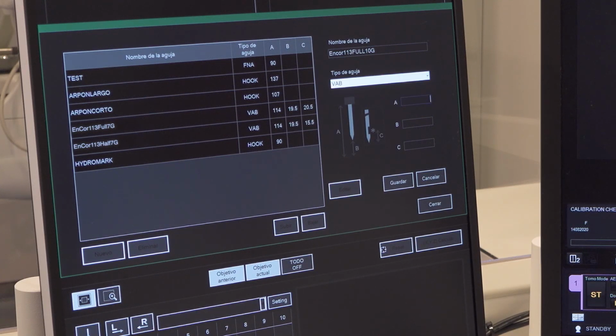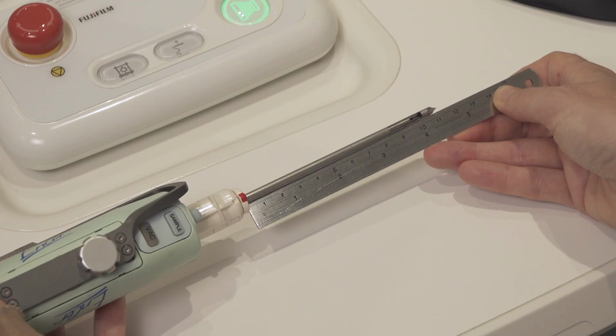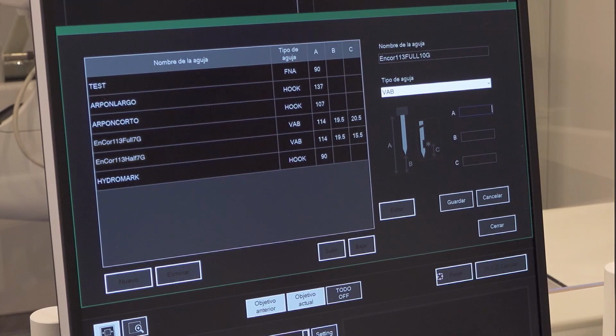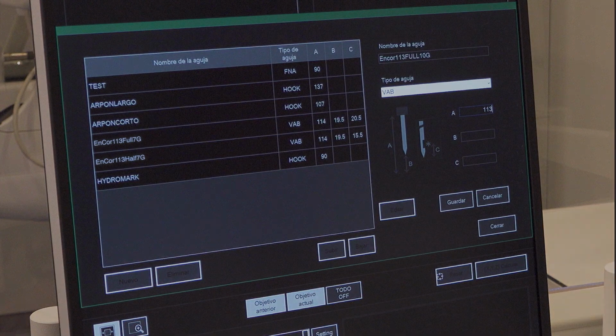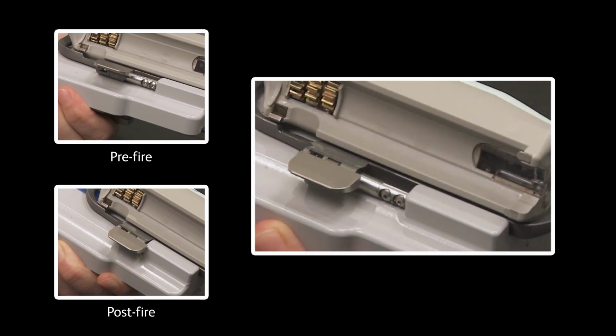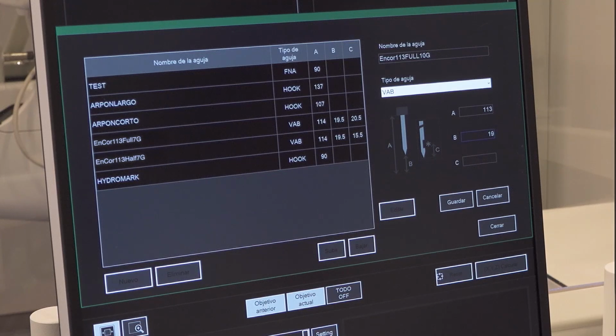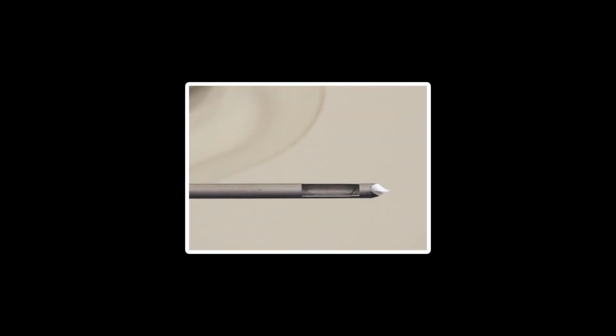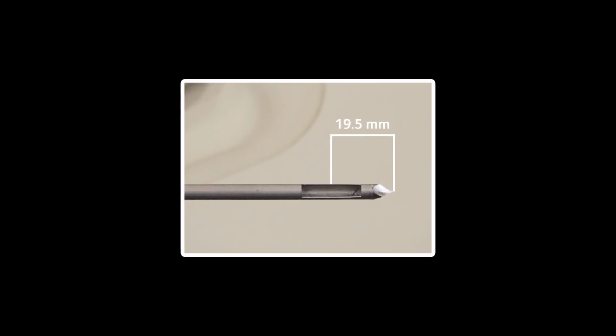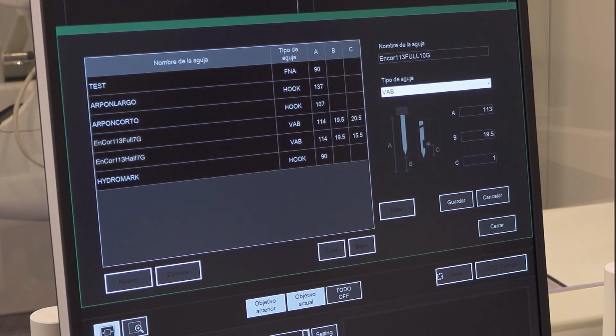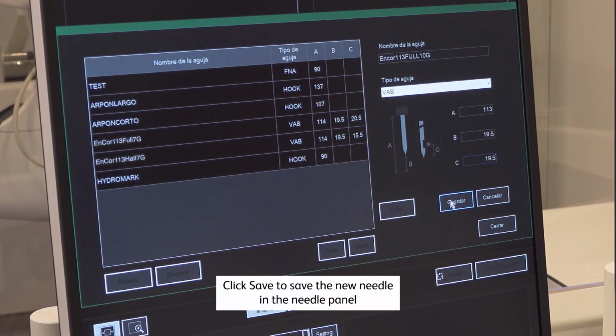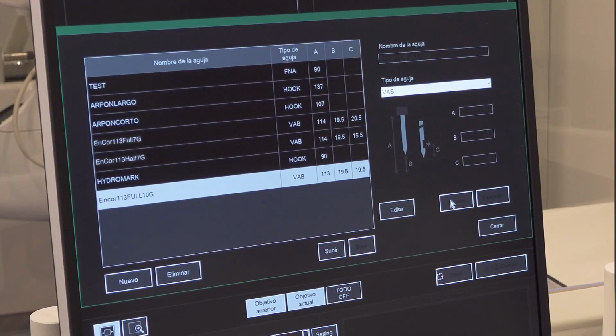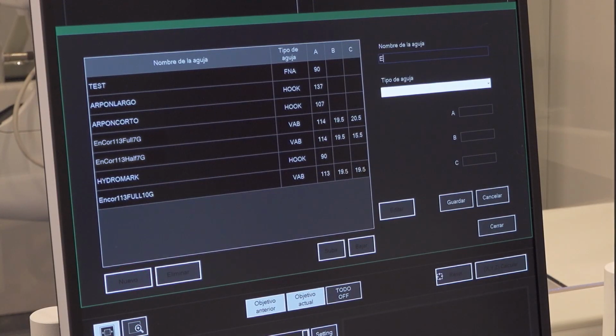Three measurements must be done, and values entered in the dedicated field. A. Total needle length. B. EnCor stroke value. C. Distance from the center of the notch to the tip of the needle. Repeat the steps for adding EnCor 113mm 10G half notch.